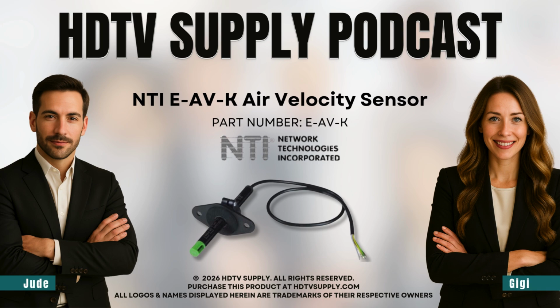The specs are impressive: a flow range of 0 to 2,000 feet per minute, about 0 to 10 meters per second. Here's where it gets interesting on precision: general accuracy is plus or minus 60 feet per minute, but it's paired with a proportional accuracy of plus 4% of whatever value it's measuring. That proportional accuracy, that's the key insight.